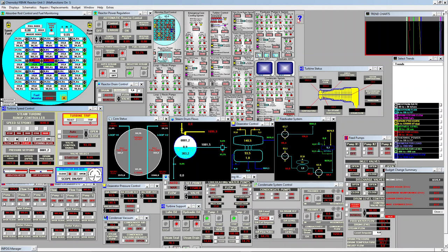What we will do to refuel is go line by line. When I find it appropriate to do a refueling, I will decrease the power set point to 95 or 90%. At this power set point, we will extract two fuel bundles from each one of the channels and throw them to the spent fuel here, and then replenish this channel with two new fuel bundles.